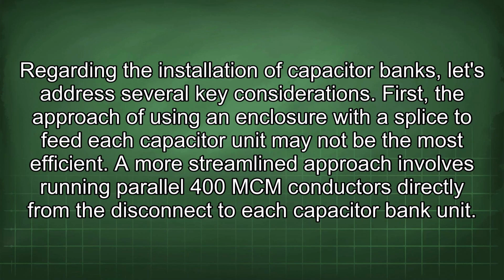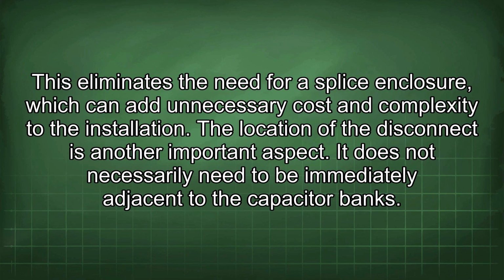Regarding the installation of capacitor banks, let's address several key considerations. First, the approach of using an enclosure with a splice to feed each capacitor unit may not be the most efficient. A more streamlined approach involves running parallel 400 MCM conductors directly from the disconnect to each capacitor bank unit. This eliminates the need for a splice enclosure, which can add unnecessary cost and complexity to the installation.